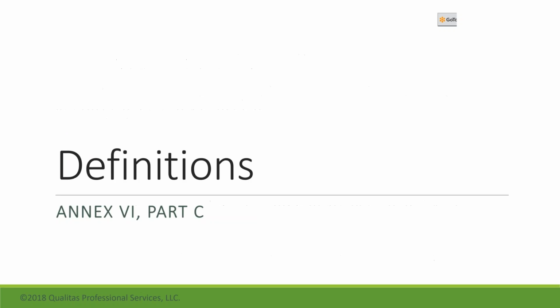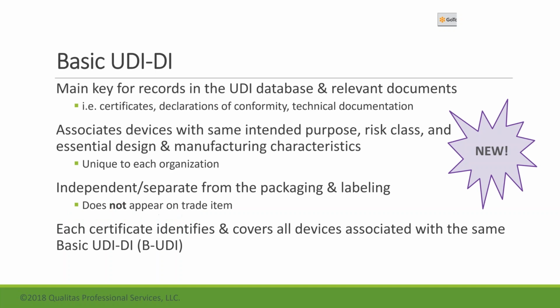So let's talk about some definitions. Now remember, these definitions are going to be primarily based off of Annex 6, Part C of the MDR. And I'm going to start with the basic UDI-DI because this one tends to cause a lot of confusion for people. This is a new concept in the MDR that the FDA does not have.